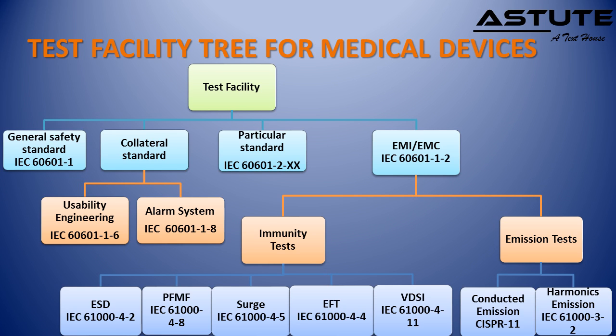We conduct tests as per different EMC standards for different immunity tests and different emission tests. In the immunity tests, we can test the compliance of equipments for ESD, PFMF, surge, EFT, and VDSI, etc. as per medical devices limits. In the emission tests, we can test the emission of noise from the equipments with the help of conducted emission, radiated emission, and harmonics emission, etc.